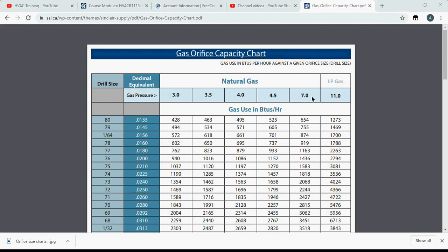We'll say we're working on a residential gas-fired furnace, and we are using 3.5 inches of water column for our manifold pressure, and we want to see how many BTUs per burner we are putting out. I must also add, you need to know the orifice size. So you're going to have to look at the orifice inside the furnace, either with a magnet or some sort of mirror, and read the number that is stamped on it.